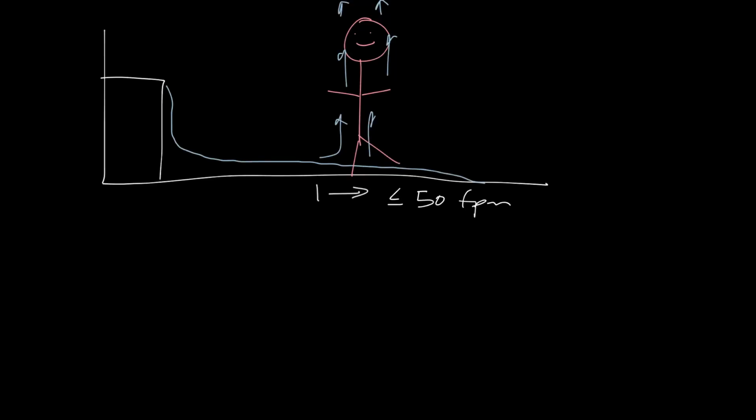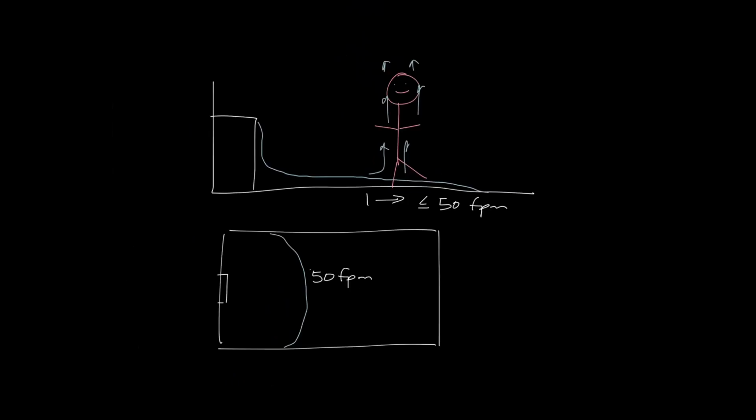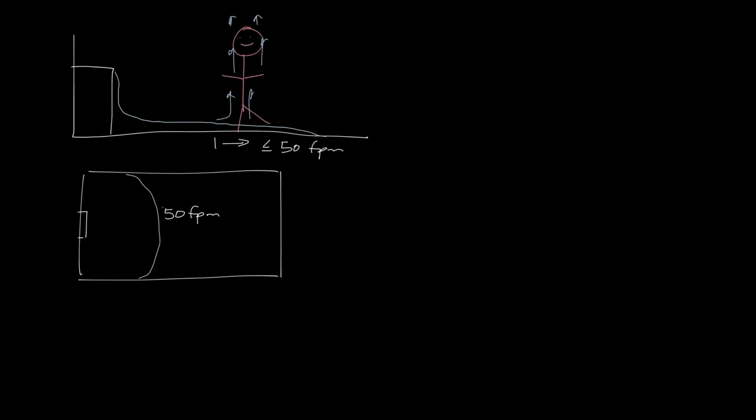So let's draw this from the top. If the diffuser face is supplying at, say, 90 feet per minute, you'll have an area that can't be occupied until it gets to 50 feet per minute. This is called the adjacent zone, or sometimes called the clear zone. And you really don't want people sitting in this area for hours on end.